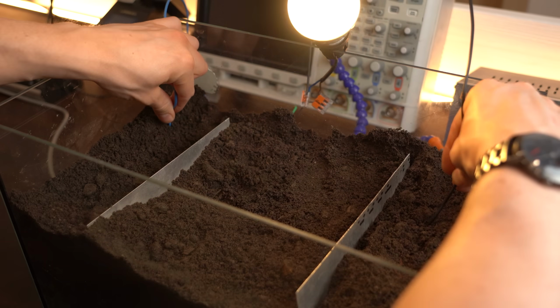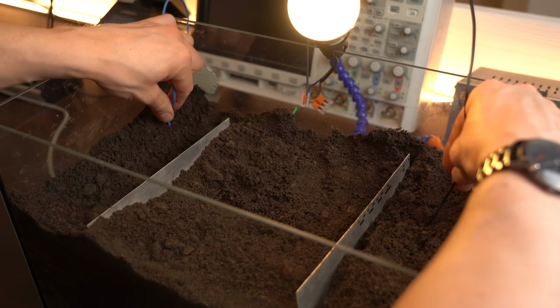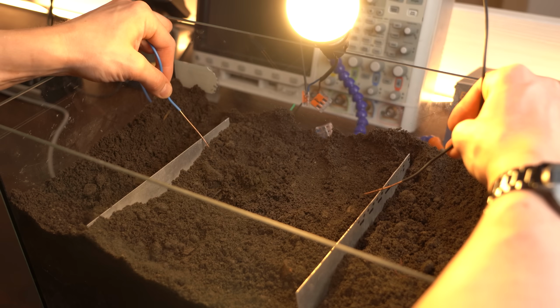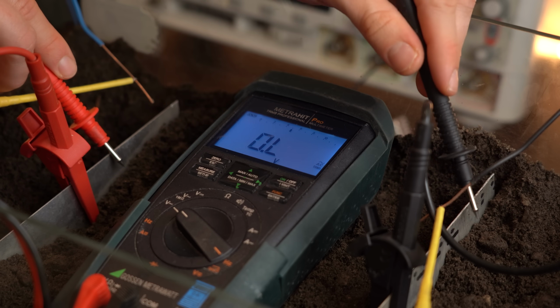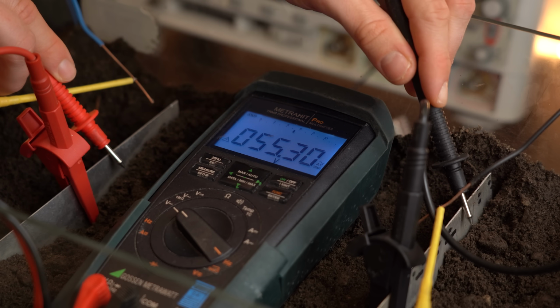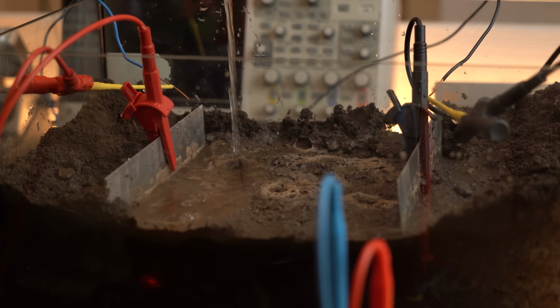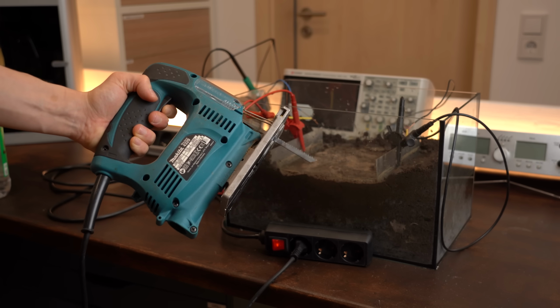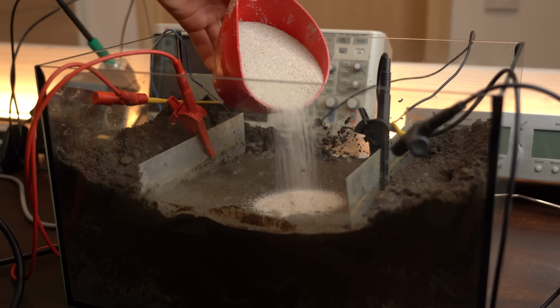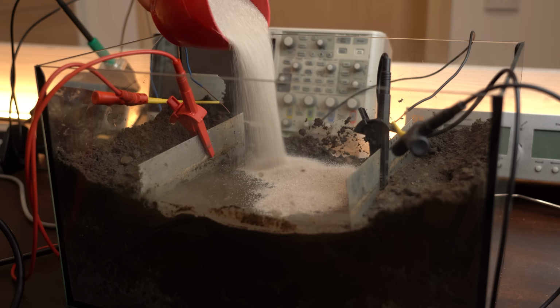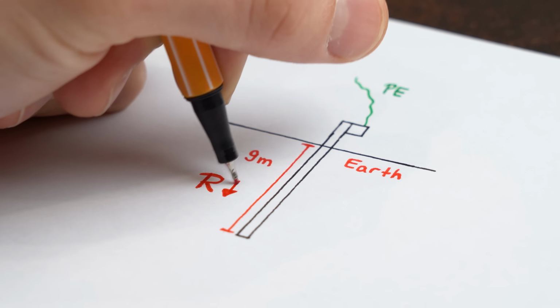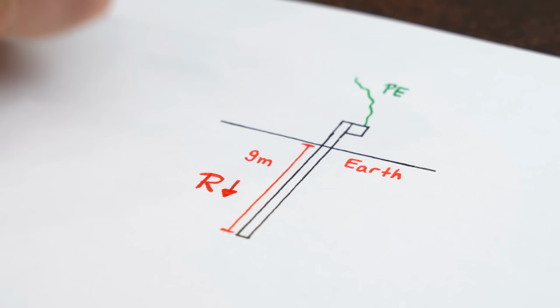That rod is pushed into the earth for sometimes up to 9 meters. Now, as we discovered earlier, the earth can be used to conduct electricity. In my case though, the resistance is still quite high with a voltage drop of around 55 volts, and of course it changes when more or less moisture gets introduced, or when sand layers appear. But with such a long rod, you usually get a pretty low resistance.